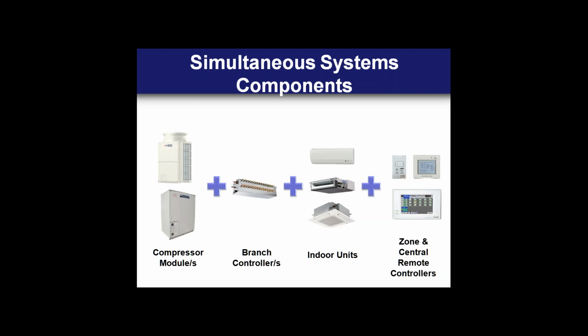That branch controller doesn't provide the throttling, though. It just provides and dictates the mode that's available to a respective indoor unit, or the state of the refrigerant that's available to that indoor unit. All the throttling and all the logic is comprised within the indoor units themselves. In fact, these systems can be installed without any additional controls. That's usually not recommended, but again, that logic is contained within the equipment.